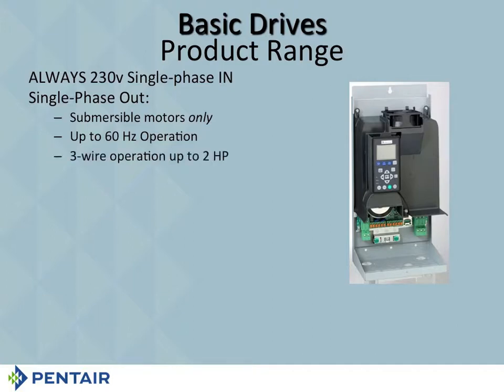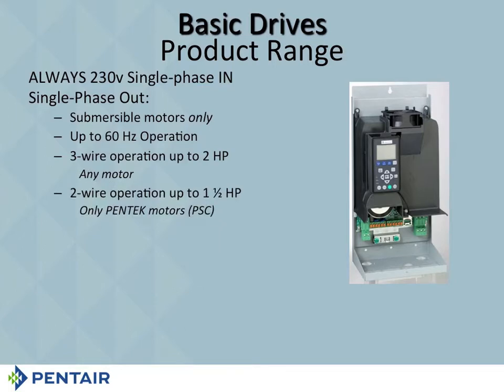If you want to, you can do 3-wire operation because single phase is 3-wire or 2-wire. If you're going to do 3-wire operation, you can go up to 2 horsepower. All right? Anybody's motor. It doesn't matter whose motor it is. You can use any motor up to 2 horsepower. If you want to do 2-wire operation, of course, you're only going to go to 1.5 horse because that's all the higher 2-wire motors go to.